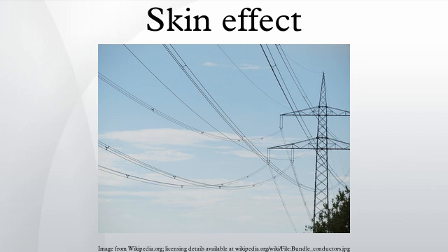sharp bends where the metal is compressed inside the bend and stretched outside the bend. The shorter path at the inner surface results in a lower resistance, which causes most of the current to be concentrated close to the inner bend surface. This will cause an increase in temperature rise in that region compared with the straight area of the same conductor.